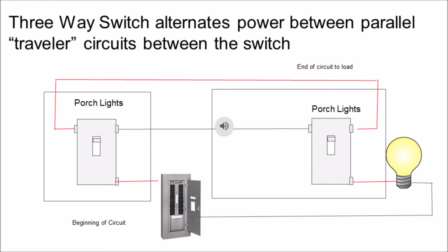This is interesting because some of the smart home light switches require rewiring the light switch and actually taking it out of the circuit, routing the power circuit through a controller tucked away behind the light switch in the junction box, while rewiring the actual light switch as a low voltage relay rather than a traditional 120 volt traveler switch. A particularly hard inspector might suggest that a relay on the wall is not the same thing as an actual electrical switch on the wall.